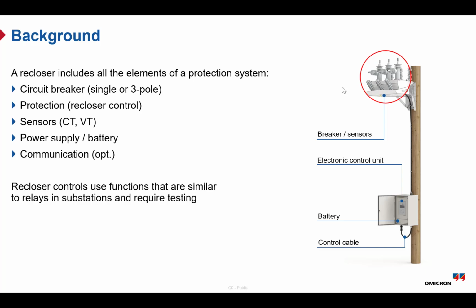This is the brain of the system. It takes all the input signals and makes decisions based on the protection logic. We also have sensors like current transformers or Rogowski coils, and sometimes voltage sensors. This provides the measurement inputs needed for protection functions. Next is the power supply. Normally the unit is powered from the grid, but it also includes a battery backup. This is important to keep the controller active even if there is a loss of supply, so it can continue to operate and respond to faults.